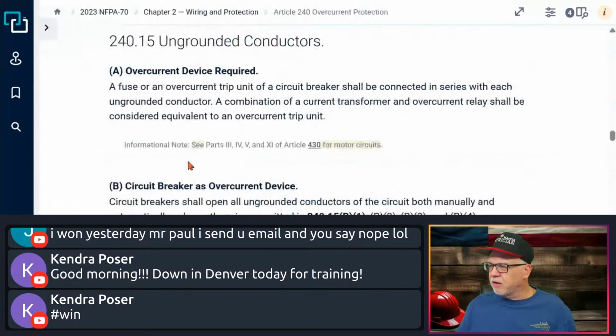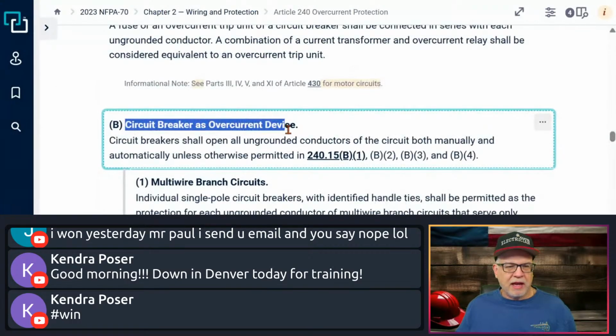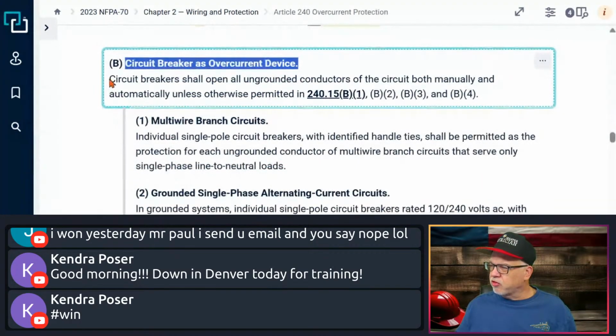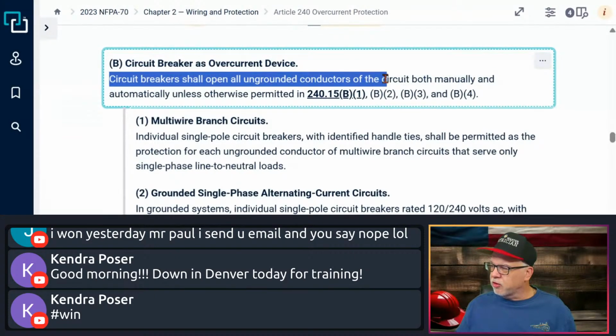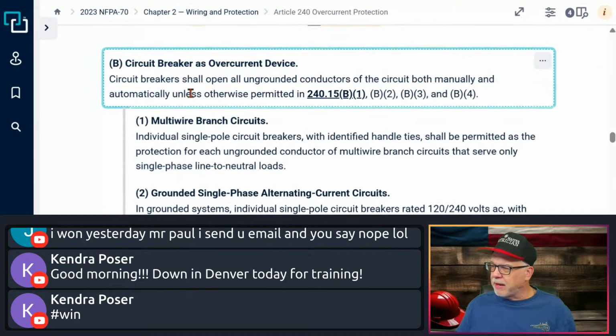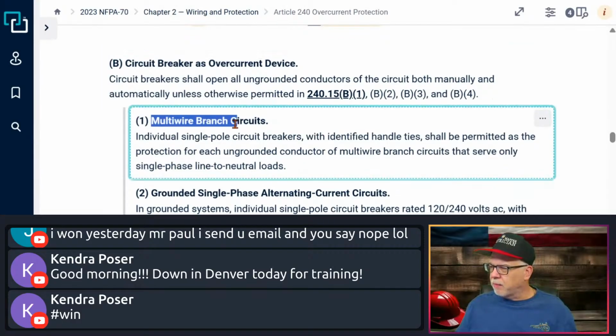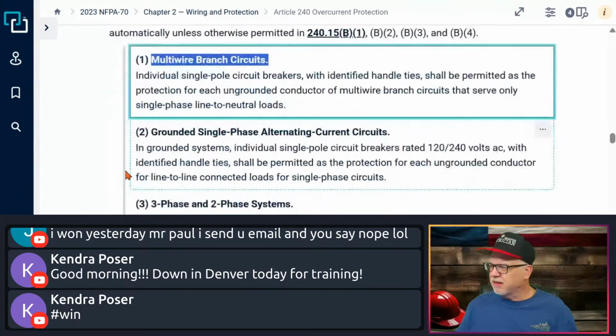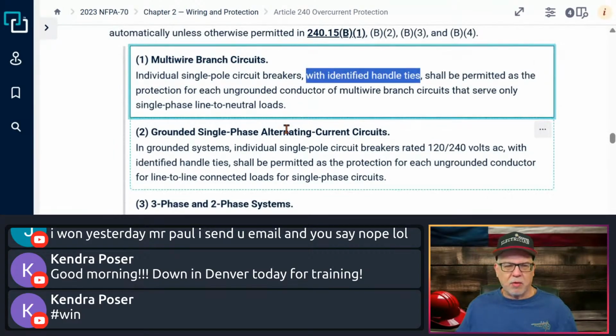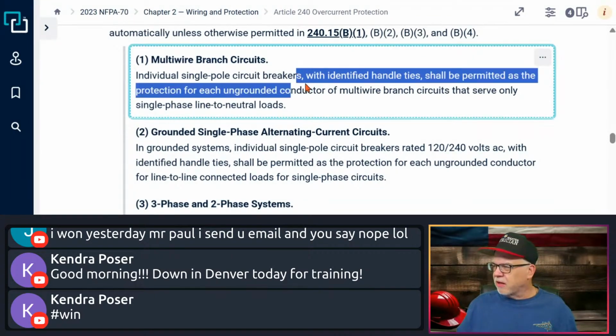And we're going to look at 240.15. Let's move this down. Okay, so here is your circuit breaker as overcurrent devices. Circuit breakers shall open all ungrounded conductors of the circuit, both manually and automatically, unless otherwise permitted in 240.15(B)(1), (B)(2), (B)(3), (B)(4). Okay, so you've got, here's a multi-wire branch circuit we talked about that I just mentioned. All right, so individual single pole circuit breakers with identified handle ties, that's important. If you're on an exam, low-hanging fruit, identified handle tie, not a piece of wire, not a screw, not a 6-32 stuck through there with a nut on the end of it, right? Even though they probably work, that's not going to work. It's got to be identified handle tie.